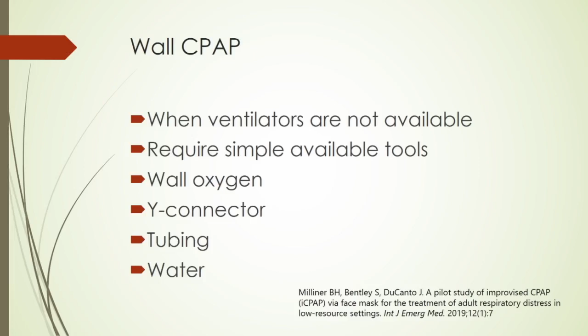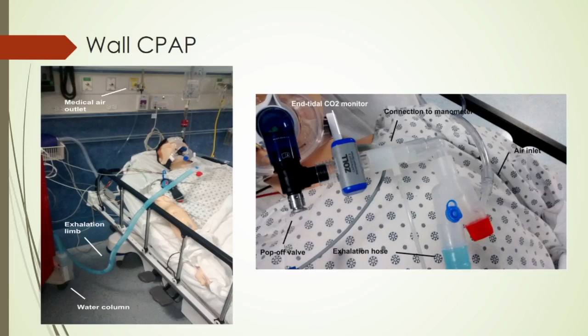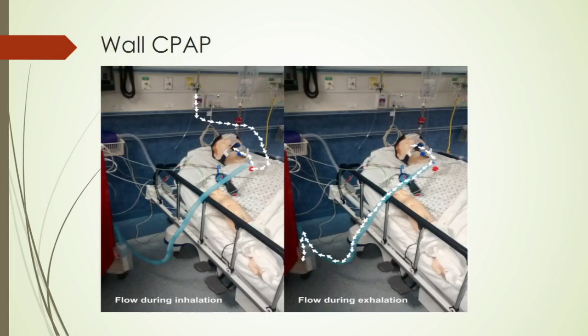And this is what it looks like. This is a mannequin, obviously, but let's say your patient's over there. You basically need tubing to allow oxygen to be delivered from the wall supply into that closed limb where the Y connector is, as you can see on the far right. Air goes in, the patient breathes in air, and then there's an exhalation hose and a pop-off valve, and the exhalation limb is plugged into this water reservoir, and you tape the tube at 5 centimeters below the water level, generating a pressure of about 5. During inhalation, positive pressure is created by the rapid inflow of air from the outlet. During exhalation, the force required to exhale through the water gives you basically a PEEP. It's obviously not a BiPAP, it's basically just a CPAP, and it generates a little bit of pressure that you might need to improve oxygenation in such a patient. So that is another trick you can use when you don't have a ventilator available.